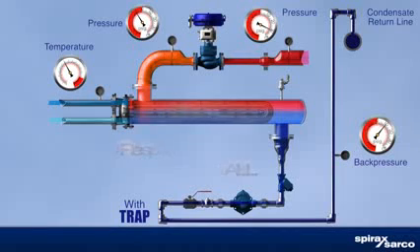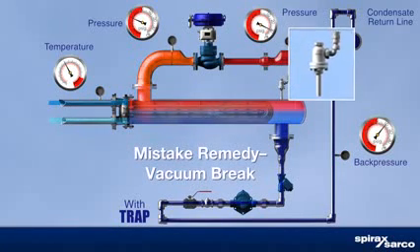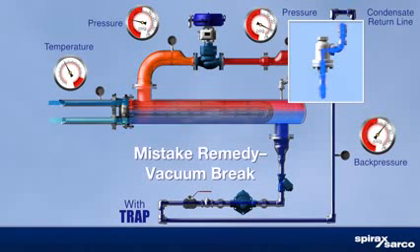Some operators address vacuum in the steam space by installing a vacuum breaker on the shell. This practice introduces atmospheric gases that dissolve readily into the cooler condensate, forming corrosives that attack wetted surfaces while doing nothing to eliminate the stall condition.